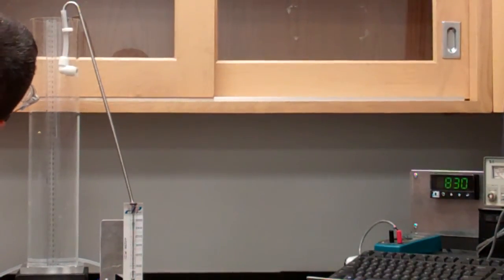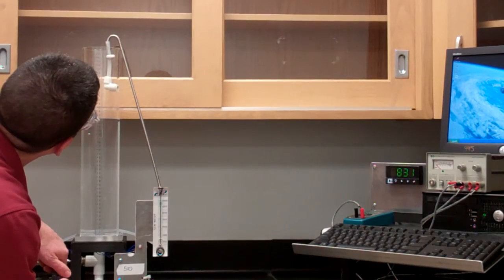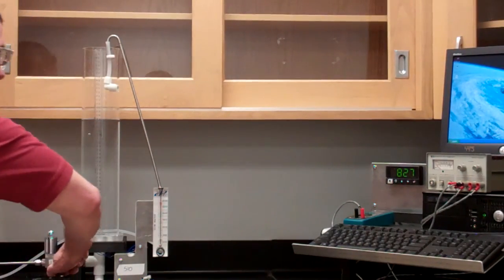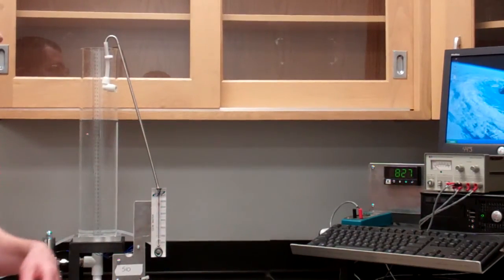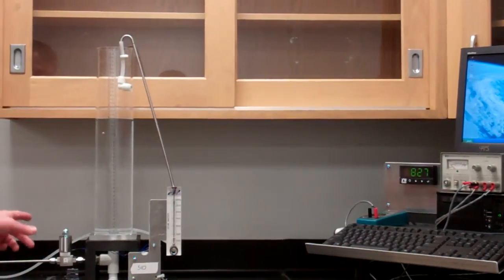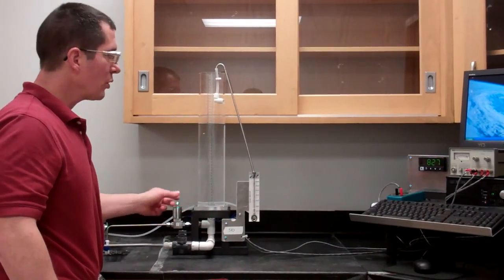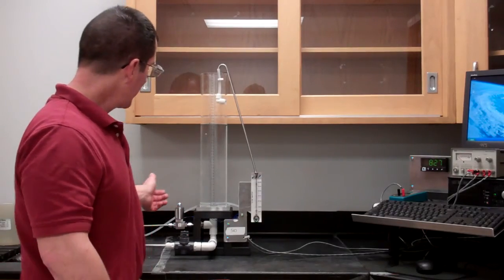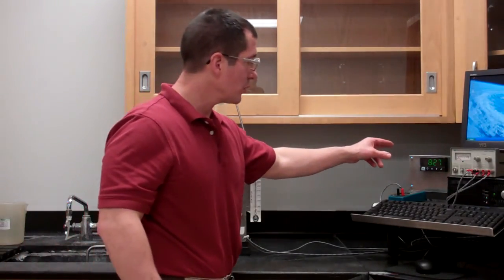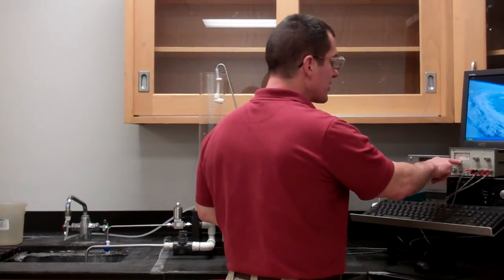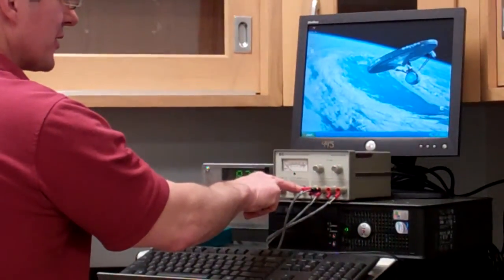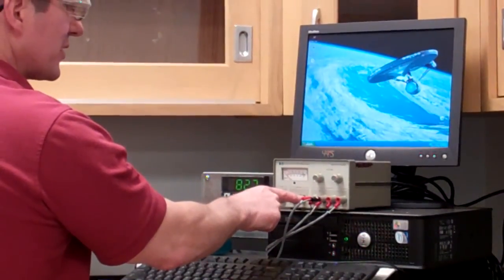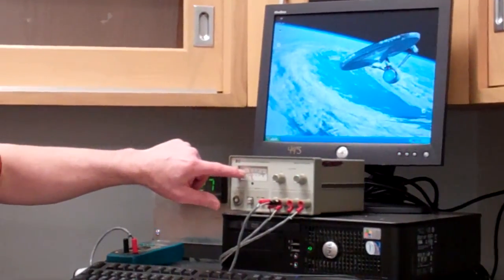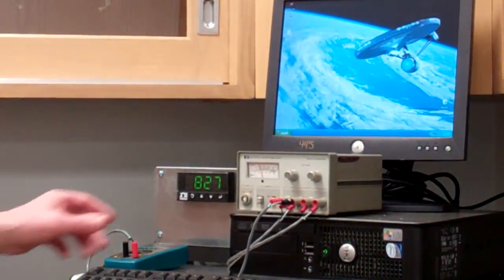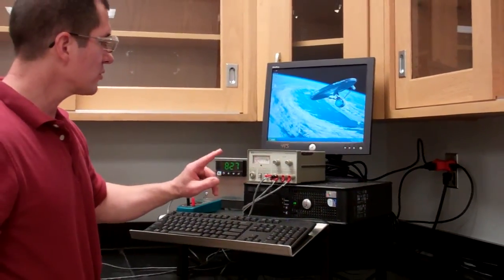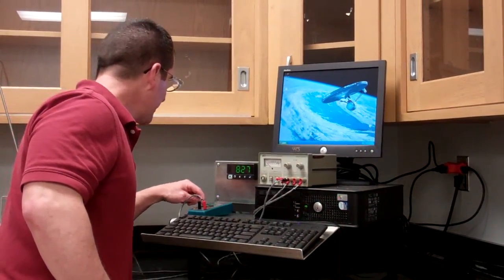A little bit much. We got to do this a little bit. There we go. So, at 30 centimeters of height, it's reading 827 counts. And now we're going to go ahead and power our control valve. This is our final control element. The input to the final control element is the output of the controller. And this is a power supply. It's already on, and it does two things. It has two channels, V1 and V2. The first channel is at 10 volts already, and it provides power to our sensor in order for it to run. And V2 is the control signal, which you'll be able to read on a multimeter here.